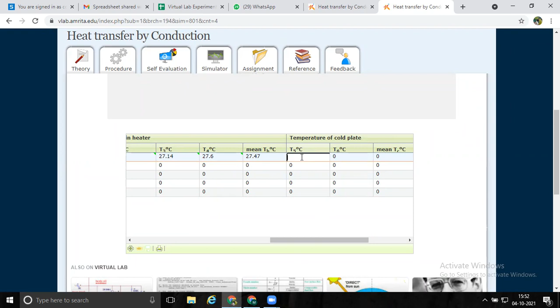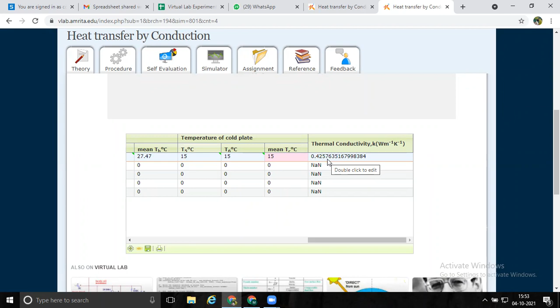Then T5 and T6 are the temperatures of the test plate on the cold plate side. T5 is 15 only, and T6 also 15. So you will get 15 degrees Celsius as the mean temperature. It will be automatically calculated by using the formula. And finally, you are getting the thermal conductivity as 0.4257 watt per meter per Kelvin.